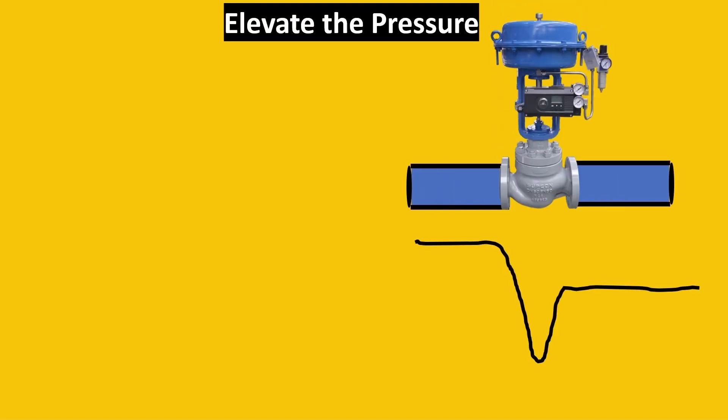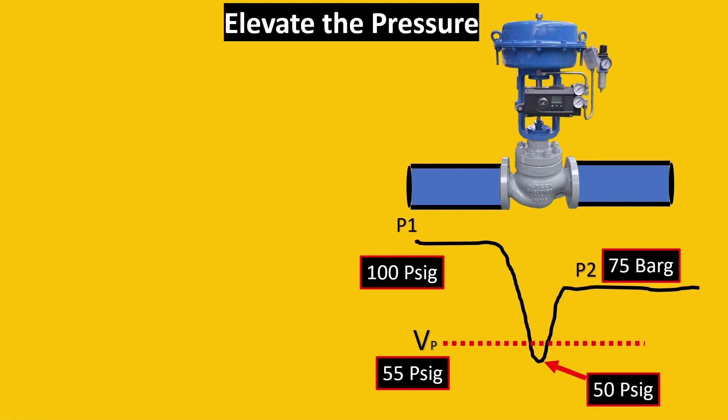Now let's look at the elevate the pressure solution. Here's your control valve and the pressure drop curve. Here's your vapor pressure. It's very clear that cavitation is going to happen here because the pressure drop is going beyond 50 psig and the vapor pressure is 55 psig.